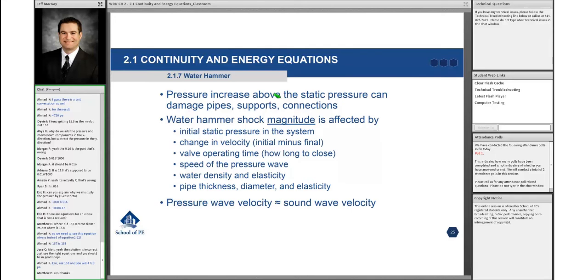ends up being like 260 psi - that's certainly possible. Pipes are rated for a certain amount of pressure, basically like a burst pressure, and if the static pressure in the system gets above that, the pipe could burst. Normal operating pressures are usually much, much lower than that burst pressure, but the water hammer can really skyrocket it and that's when we can have burst.